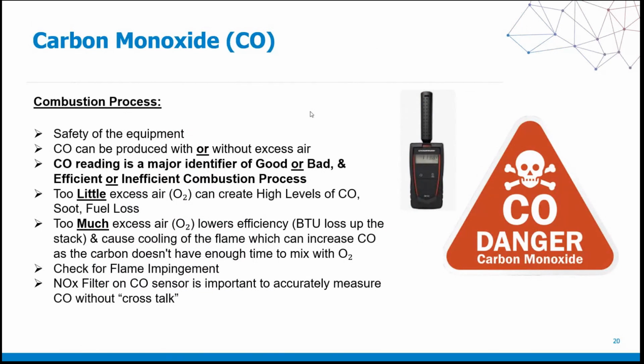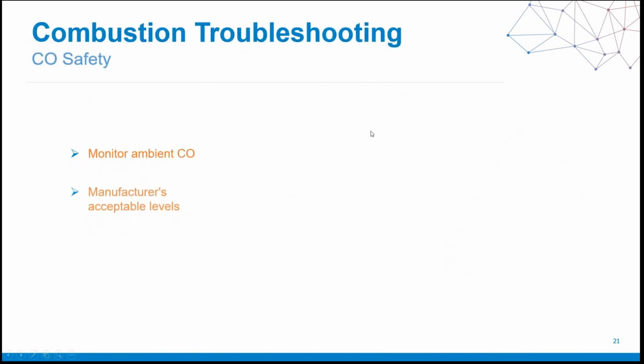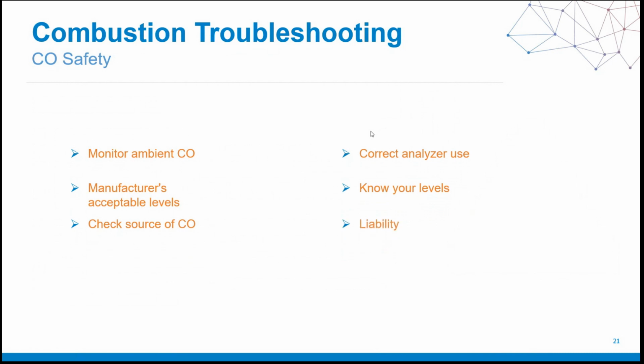So it's important that with a combustion analyzer we do two things with it. One is that we monitor the ambient CO in the space that we're in. Second is that we pay close attention to what the CO levels are on our analyzer screen when we're actually performing a combustion analysis. When we talk about combustion troubleshooting and CO safety, there are a couple of things that come to mind. The first one I just touched upon, and that is the monitoring of the ambient CO.